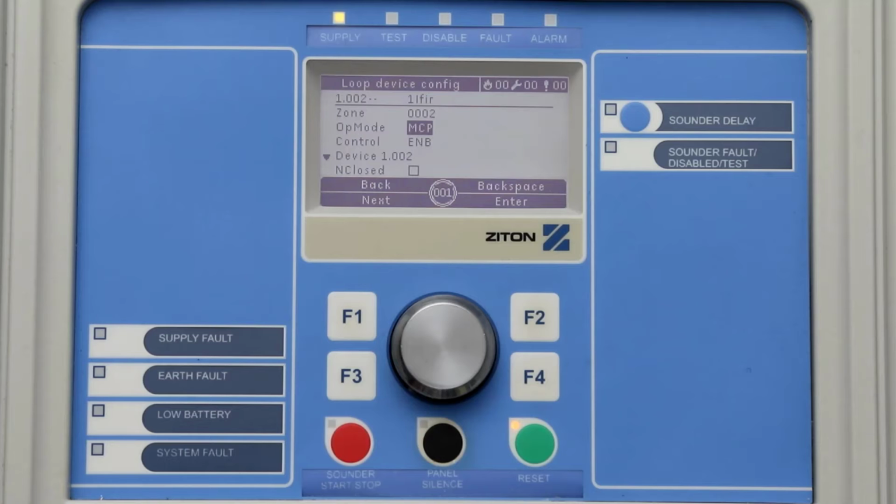The next few options will not display a fire condition on the panel if the input unit is activated. Also, any OP mode that doesn't display a fire on the panel if the device is active cannot be added into a zone. UKSB stands for UK School Bell. Using this OP mode will activate any outputs that have been configured to operate with UKSB. The output will only activate for 5 seconds, which is not configurable.